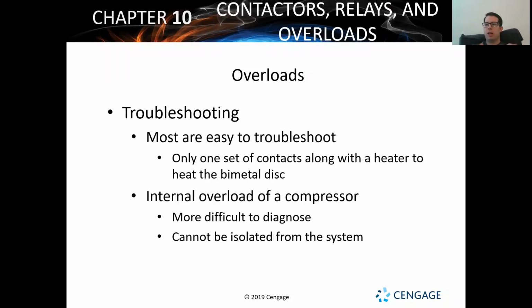Because what's going to happen? I replaced that overload. Oh, seems to be working fine now. Well, the reason why it's working fine is because you just basically reset the overload by replacing it. And it runs, and it might run for 20 minutes. It might run for an hour. And then you might leave, and you might not have to come back until the next day. And then you've got to explain to that person, oh, well, yeah, I know it was an overload, but I didn't really have the time or didn't want to look into why it tripped. I just wanted to replace the part. Yeah, they're going to love that. They're going to love hearing that from you.